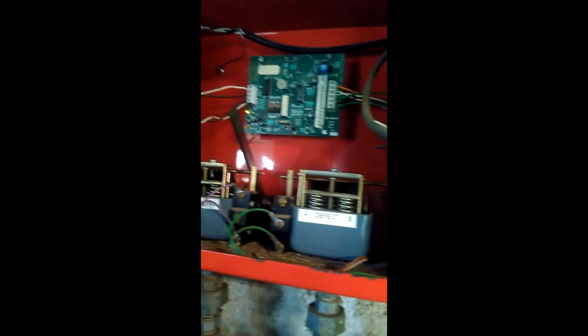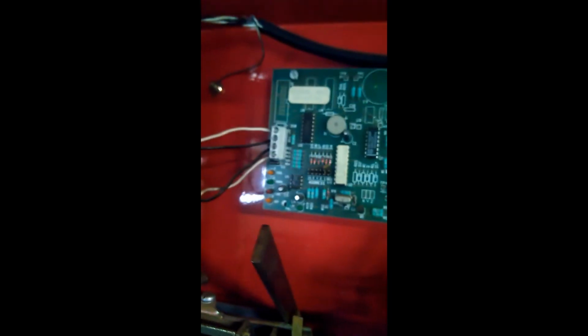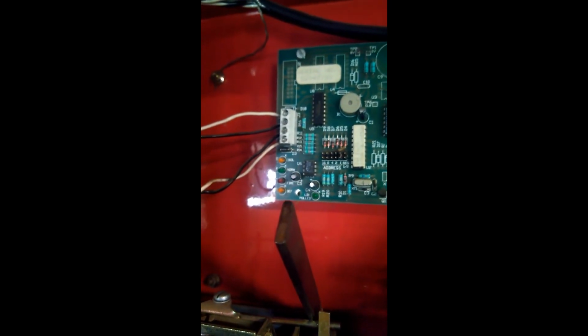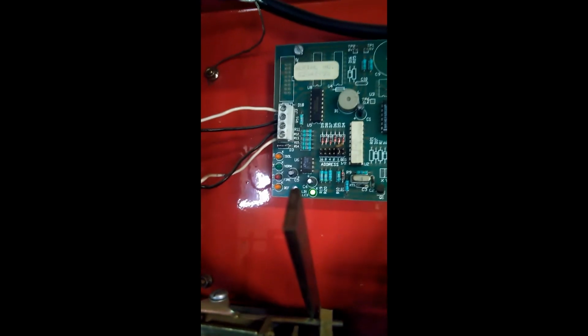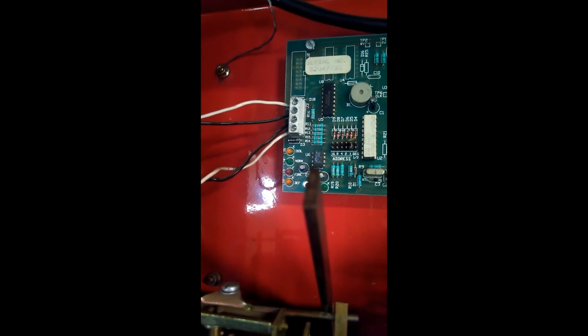So what I always do is you've got the system isolated, I put the system into test and the LED light will start flashing. Then you put the system back into normal and you'll see the LED light move from isolate to normal, and normal will be flashing. So that's what you want. Then you can come across to the test and switch that into normal. So you're back online, hooked up to the fire brigade.